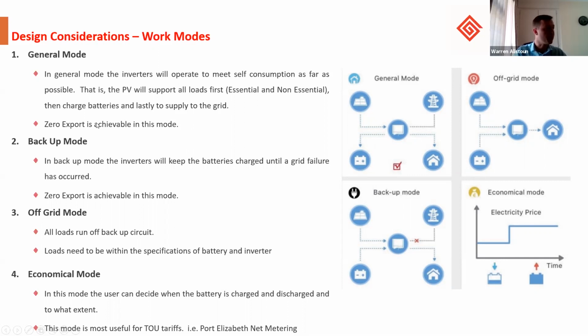The second mode is backup. In backup mode, the inverters will keep the battery charged until a grid failure has occurred, and the battery and the inverter will take over from there. Again, zero export is achievable. The third work mode, which is not very common, is the off-grid mode. In this mode, all the loads need to run off the backup circuit. So it's absolutely critical to understand that load fully so that the right product is introduced to the project.